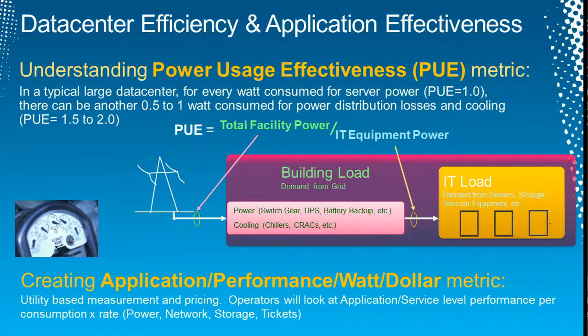The point I want to make is we've already achieved with our IT packs, Generation 4, a 1.05 PUE. This is reality. I think this is a good measurement that should be a focus for all IT operators, but it isn't the crown jewels. If you look at Microsoft, Google, Yahoo, and our PUE numbers, we're all running relatively efficient. All it tells you is how well we're using power, and that's a good thing. But we've almost reached theoretical, which is 1.